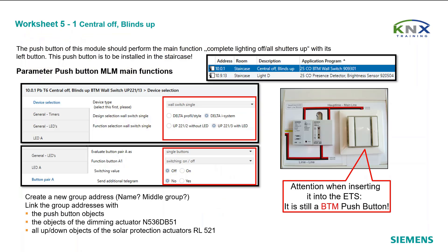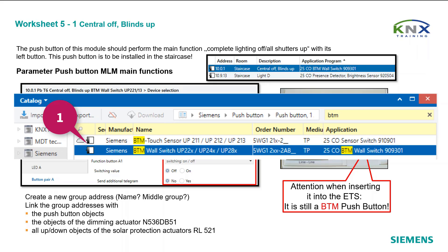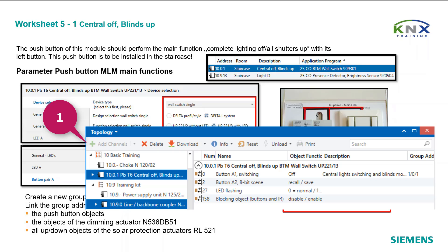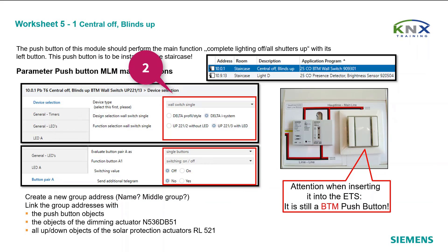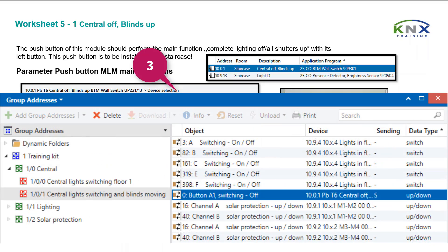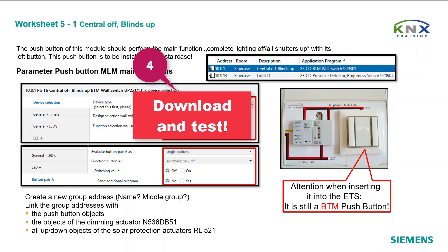Worksheet 5-1: Central off, Blinds up. The push button of this module should perform the main function — complete lighting off and all shutters up — with its left button. This push button is to be installed in the staircase. Follow the workflow: 1. Look up the new device in the catalog and insert it into your project, making sure the push button has a main line address like 10.0.1. 2. Do the parameters next. 3. Create the new group address and link it to all required objects. 4. Download and test all affected devices.